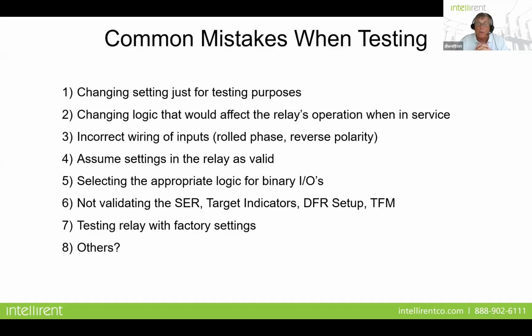Select the appropriate logic for binary IOs. Okay. Make sure if it's a Form A that you're looking at a Form A. If it's a Form B, make sure you're looking at Form B. Not validating that your sequence of events, your target indicators, your fault monitor, or your through fault monitor are set up. If you test them, okay, if you create a fault, go in and look at these different files to make sure you have them set properly.